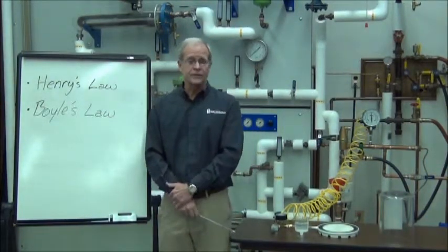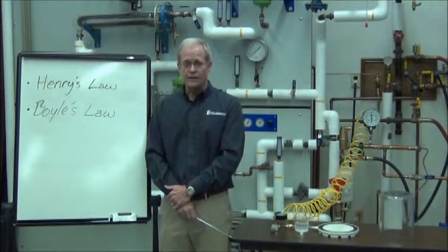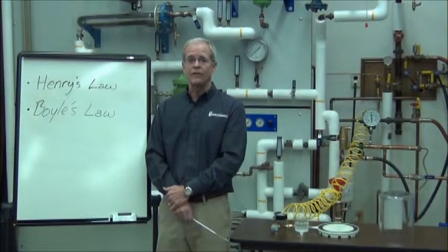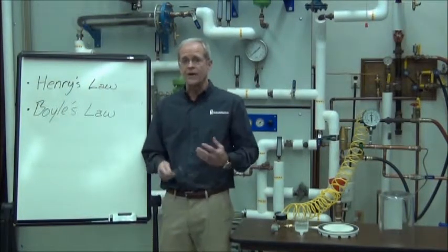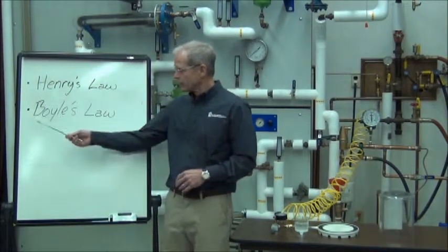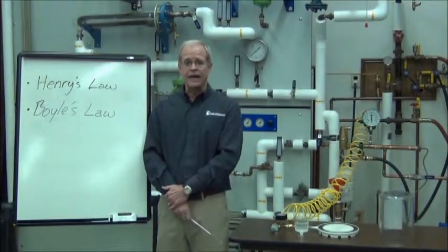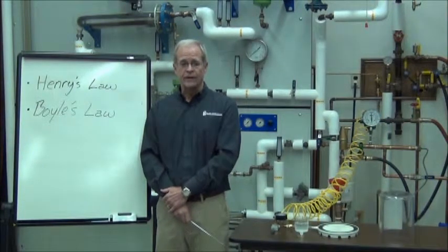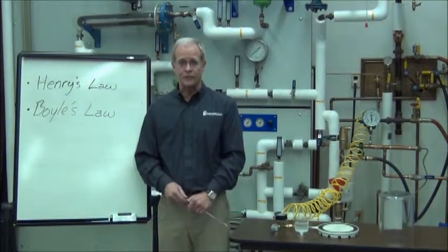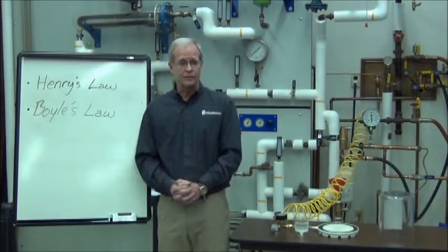Henry's Law basically says that as the pressure is reduced on the fluid, less dissolved gas can be dissolved in the fluid. So it will start to come out of solution as we reduce the pressure. And Boyle's Law says as we reduce pressure, the volume of any gas increases inversely proportionally to the absolute pressure, meaning as the pressure goes down, the volume of that gas will grow. So if you have a bubble, the bubble will get larger.